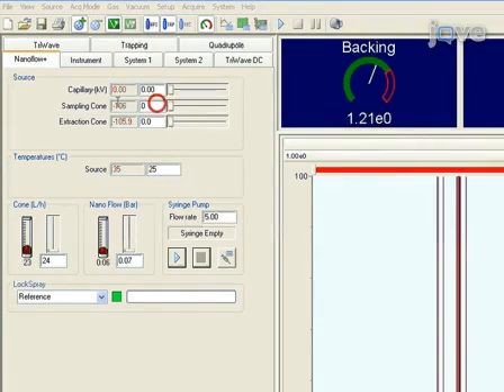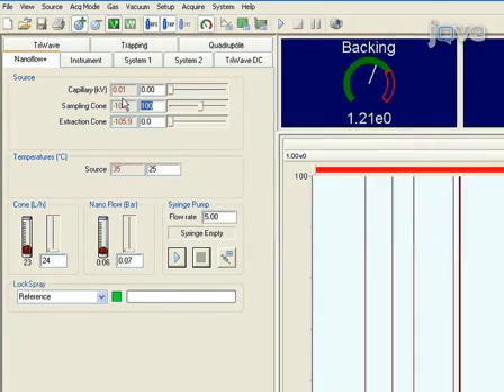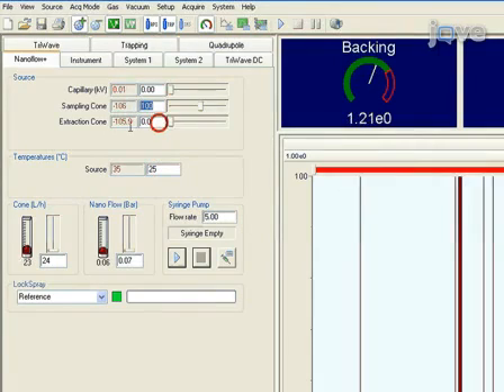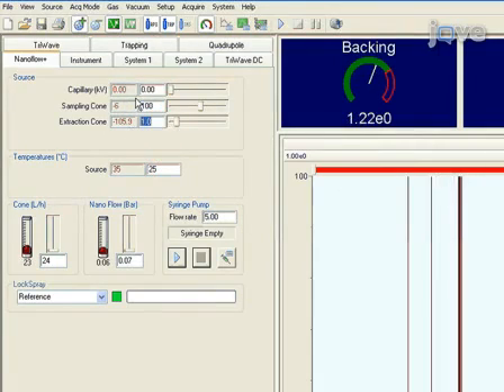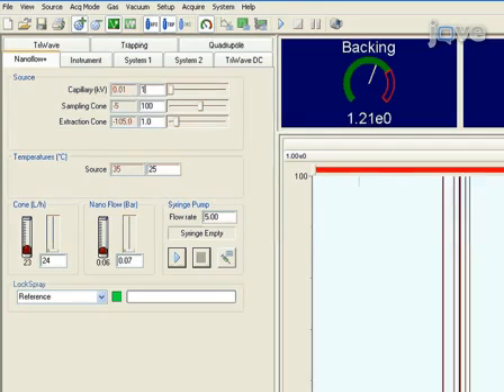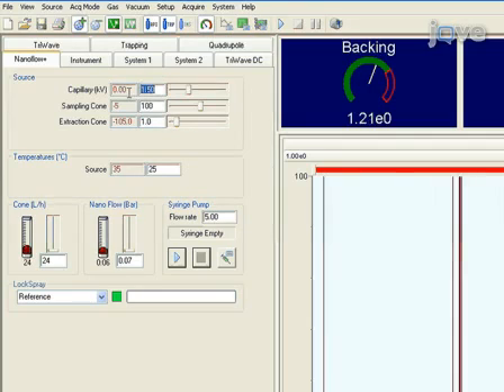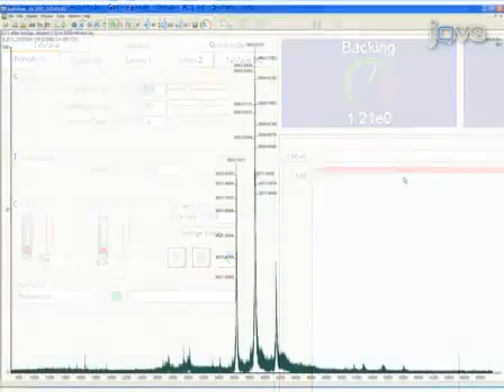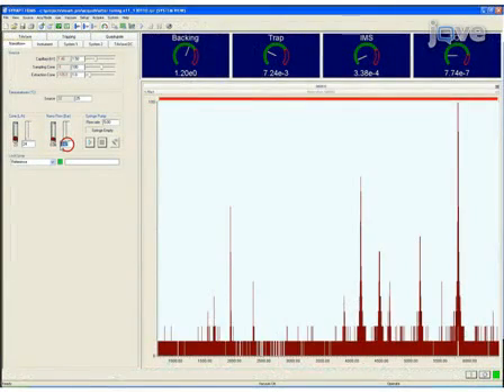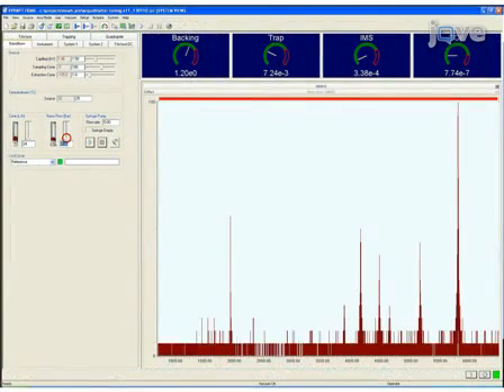Vary the capillary position, sample cone, and extractor voltages to maximize ion transmission. A possible starting point is cone voltage 100 volts, extractor cone 1 volt, and capillary voltage 1.5 kilovolts. Check the resulting change in the spectra. Optimize these parameters in combination with the nanoflow pressure.